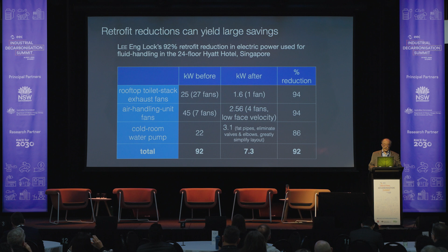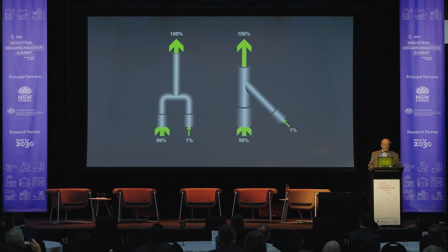Now, pumping is the biggest fluid handling task, and normally a critical pump with an in-place spare pump would be laid out like this, so the flow always goes through 2 right-angle bends, friction. So why not lay it out like this so the main flow has no bends and also fewer valves? The same logic applies with identical pumps in tandem, a very common arrangement. So to wring out the friction that wastes about 15% of US electricity, we simply use big pipes and small pumps, not small pipes and big pumps. And notice we've raised up that little blue pump to meet the pipe rather than dipping the pipe down to meet a pump on the floor and then back up again.